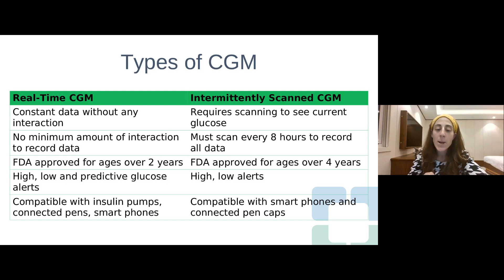And these devices must be scanned at least every 8 hours to be able to record all the data. So if it goes longer than 8 hours, some of that data just wouldn't be recorded when we go to download it. FDA approved for ages 4 and over, depending on the device, and some do have high and low alerts now. And then there is compatibility now with smartphones and then connected pen caps. There is not compatibility with insulin pumps yet at this time for that. So we basically have these different options available.